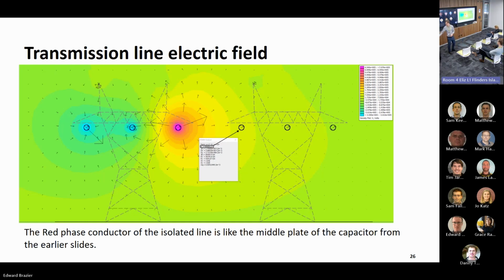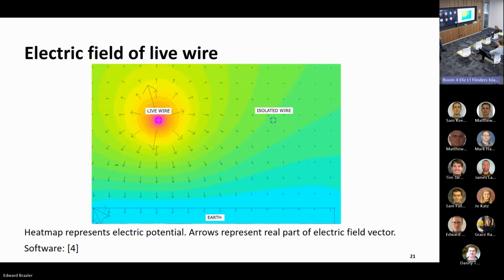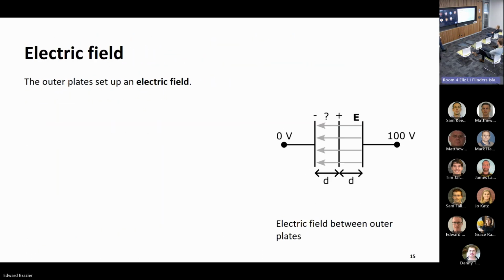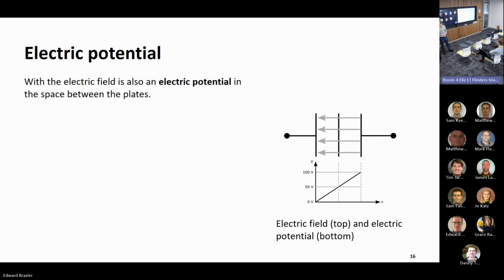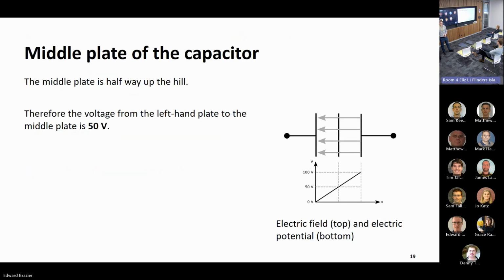Edward, I had a question on the earlier slide. You showed the relationship between the two plates of the capacitor with a mid-span section, and you drew that relationship as entirely linear. But when we look at the field strength, the voltage per unit distance, you said the potential across that mid plate would be 50 volts if it's in the middle. But the field strength isn't entirely linear with respect to distance between the two conductors, is it? You have a much higher strength closer to the conductor, and it's not a linear decay to earth.